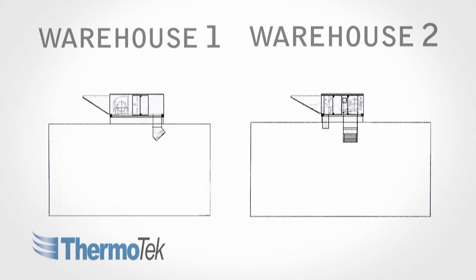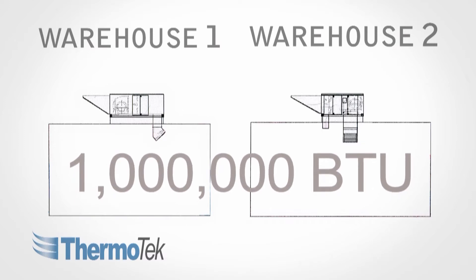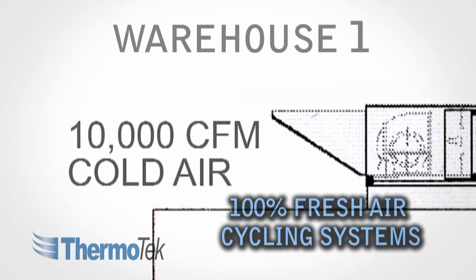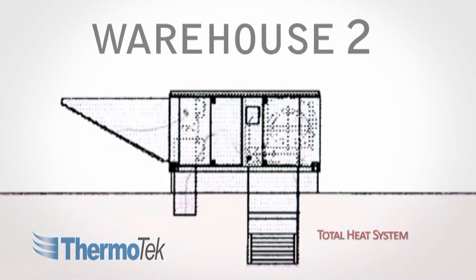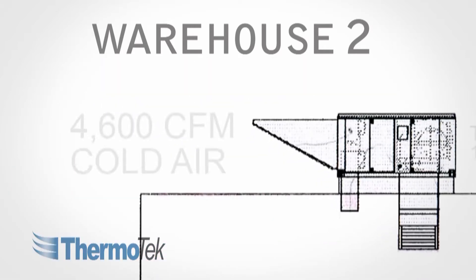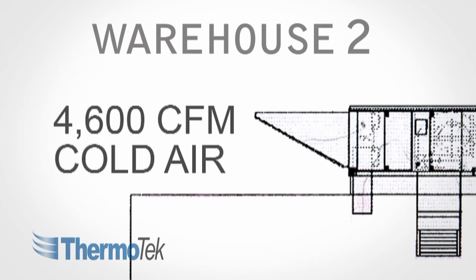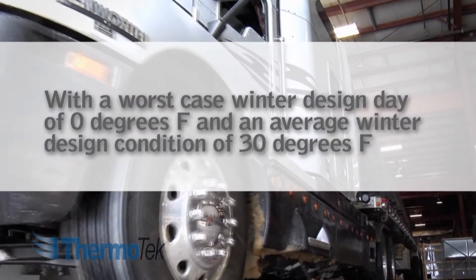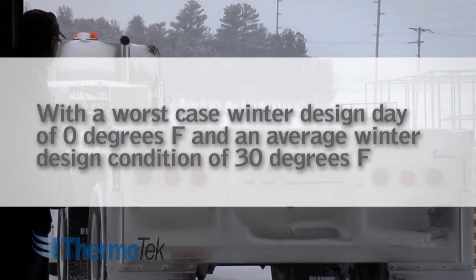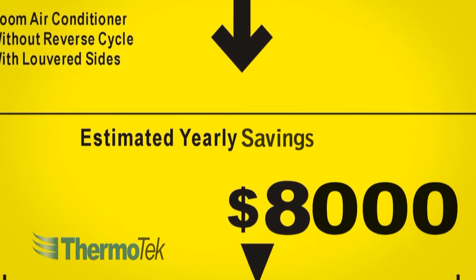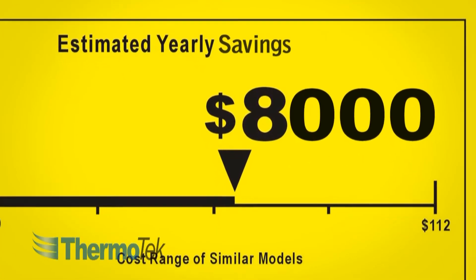Let's compare two warehouse facilities in an energy analysis, both requiring 1 million BTU of heating. Warehouse 1 is being heated by a 100% fresh air high temperature cycling system. Warehouse 2 is being heated by a total heat recirculation system. As you can see, warehouse 2 requires far less cold fresh air to heat in order to meet space demands. With a worst-case winter design day of 0 degrees Fahrenheit and an average winter design condition of 30 degrees Fahrenheit, this equates to over $8,000 in annual gas consumption savings alone for a single unit.